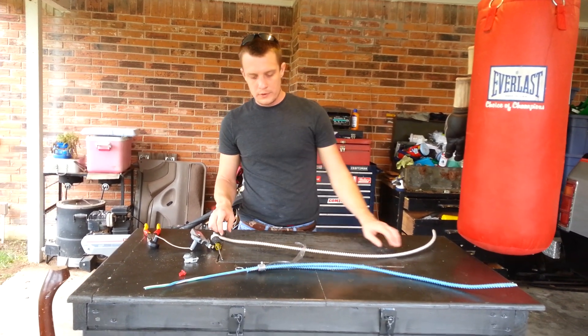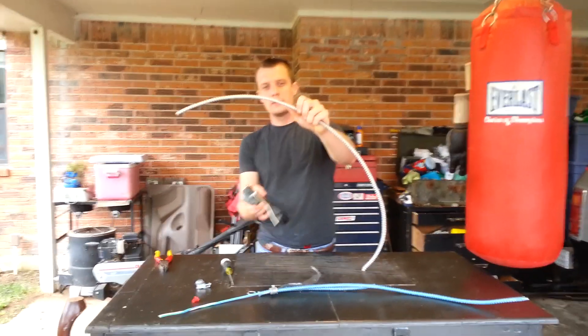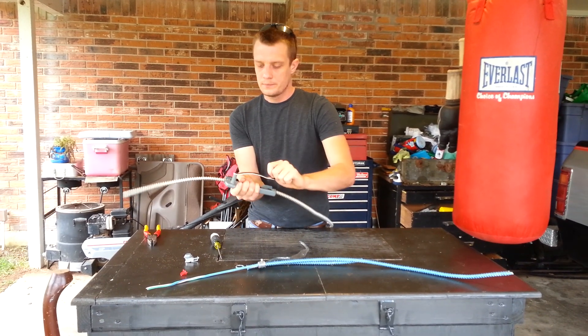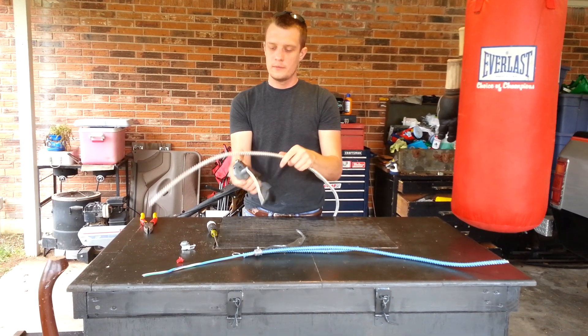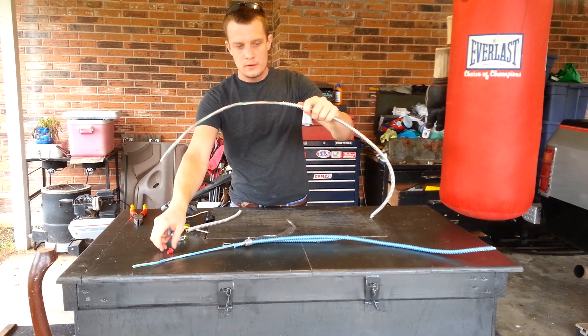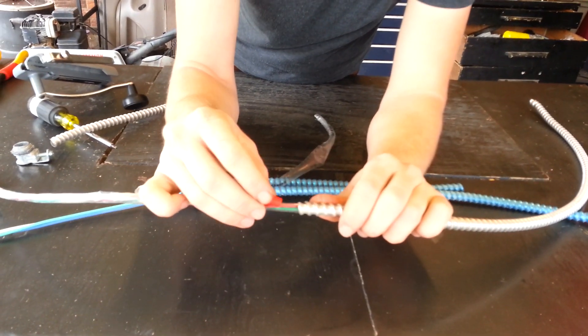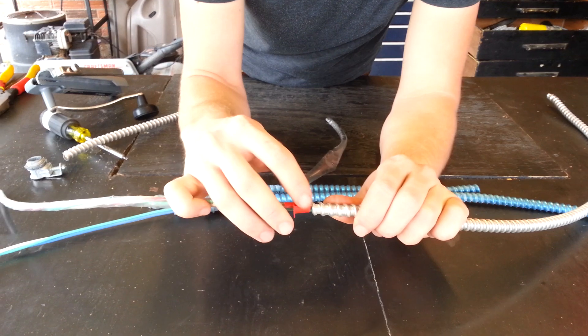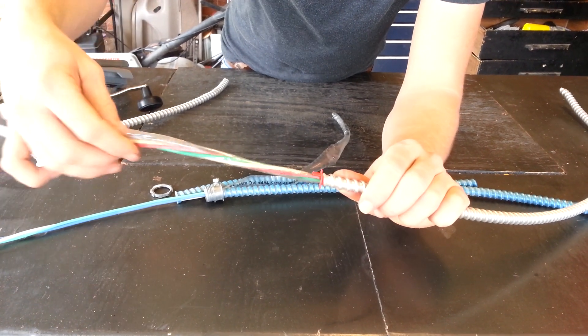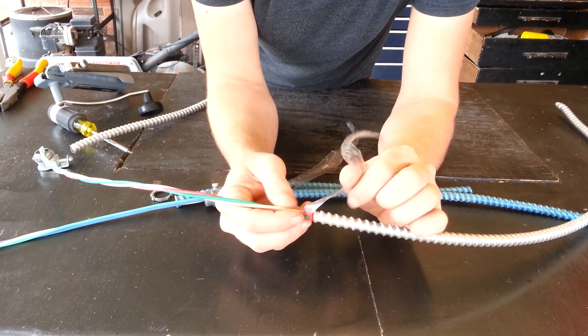We're going to do the same thing again, but this time with the aluminum MC. Take about that much length and put it into your roto-split. Firmly press down on it. There you go — the MC should just come off very easily. At the longest point of the cable, you take your anti-short, line up the center of the anti-short with the longest point of the MC, and put it in like so. Take your plastic insulation, center it up with your center point, and pull it back.